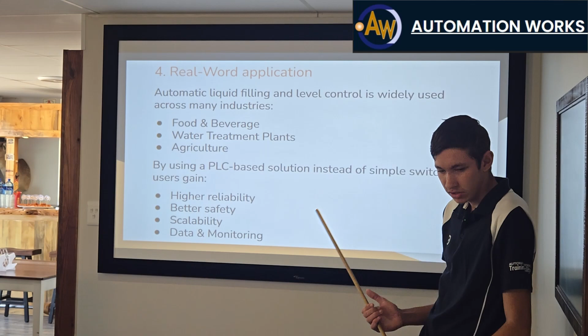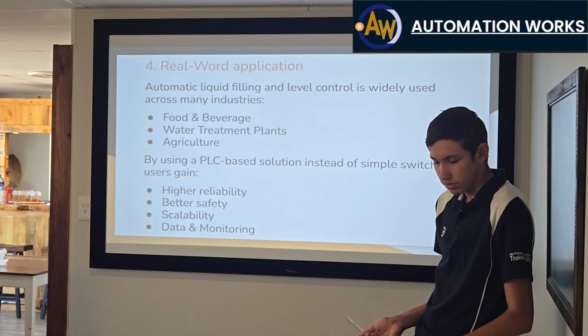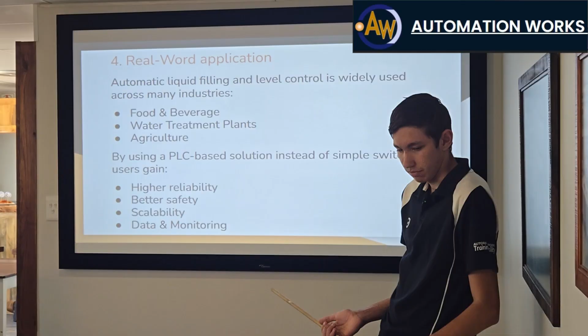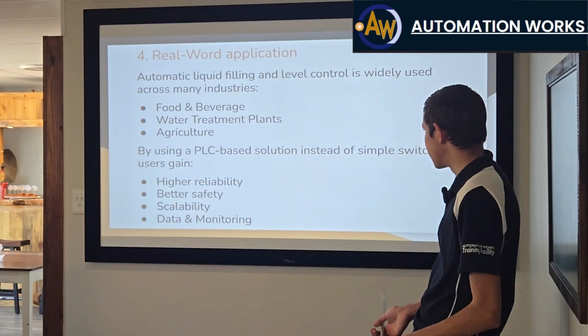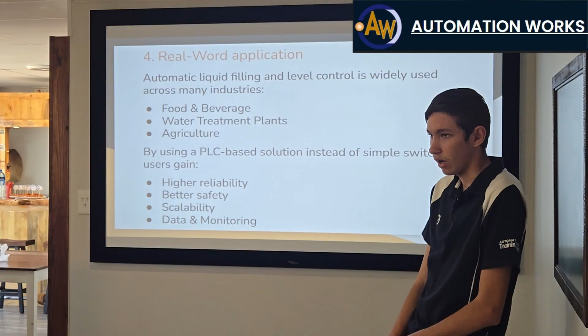By using a PLC control system instead of simple switches, users gain higher reliability and less downtime, because there are no mechanical floats to stick. There's also better safety, because I have an interlock that prevents the pump from running when the valve is open, or the valve from being open while the pump is running.